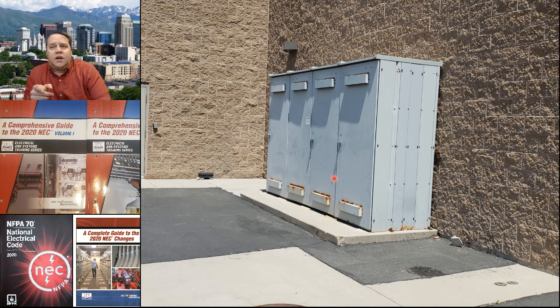Because an installation like this, I have a major problem with. I think this is the worst type of concrete pad you could possibly have, where it's 18 inches or something close to that. So the depth of the pad is measured from the closed equipment. If I look at 110.26 A1, that's how we make the measurement, with the doors closed.